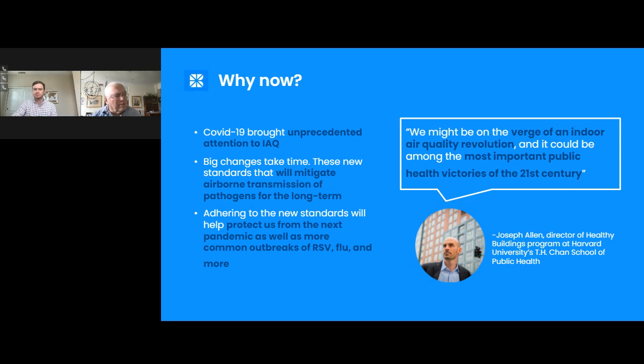In the long run there's a lot of overlap between these two approaches. These are overdue recommendations. The ASHRAE recommendations were made rather hastily and are now under review - I submitted comments, as have many others, and we'll see what comes out. I wouldn't take the current recommendations as set in stone. CDC recommendations, however, are not under review; that seems to be their settled opinion of what's reasonable, and I'd tend to agree. I think 5 air changes is more than comfort-level ventilation, but also probably feasible without complete renovation of the ventilation system.